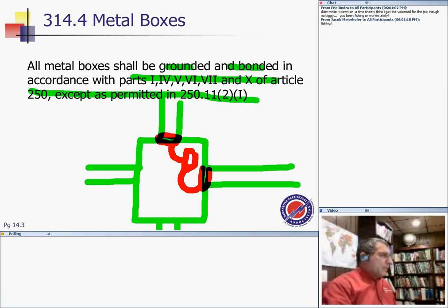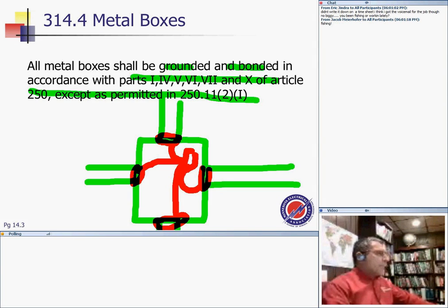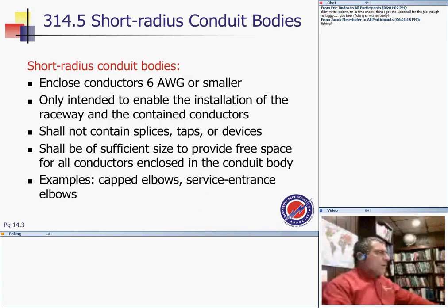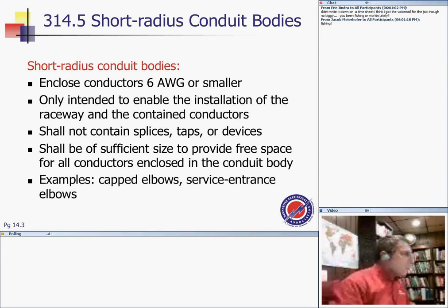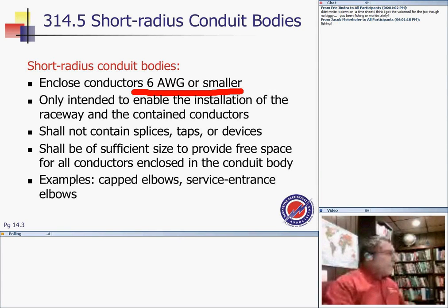And all these conduits to a grounding bar inside your box, which are bonded together. A special box, for example, is a pull box that's non-metallic, like a plastic box or something. Short radius conduit, short radius conduits or conduit bodies, guys. Enclosed conductors: look at the limitation of the conductors. One is number 6 or smaller, only intended to enable the installation of the raceways and the contained conductors.